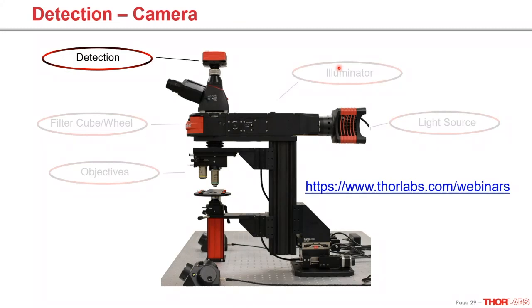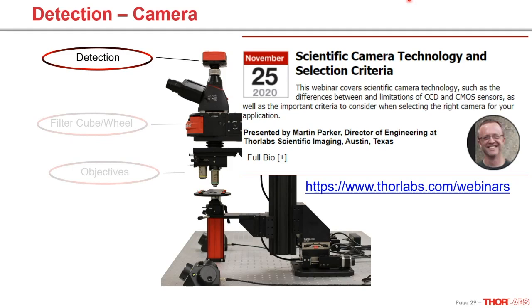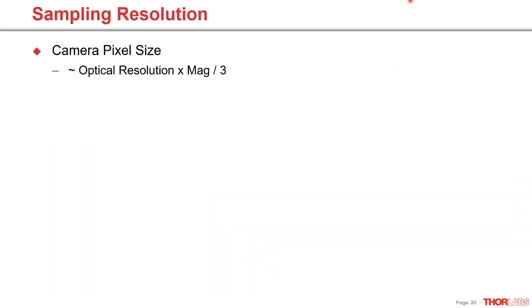Next I'd like to go into detection, focusing on cameras. We had an extensive discussion on camera technology in a previous webinar by Martin — I encourage you to check that out. For fluorescence microscopy, a camera determines your sampling resolution — not the optical resolution, but the sampling resolution. Camera pixel size plays a key role. As discussed in Martin's webinar, the pixel size should be about a third of the optical resolution (the fundamental limit) multiplied by the magnification of the objective, assuming a 1X camera tube.